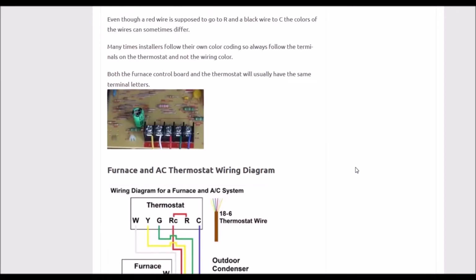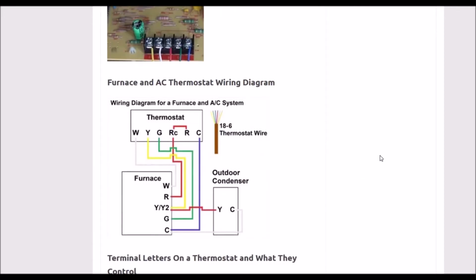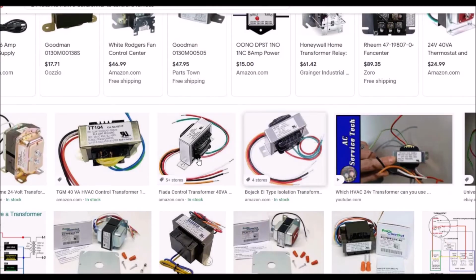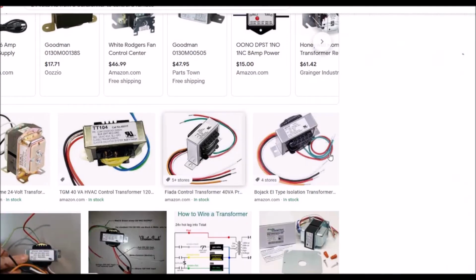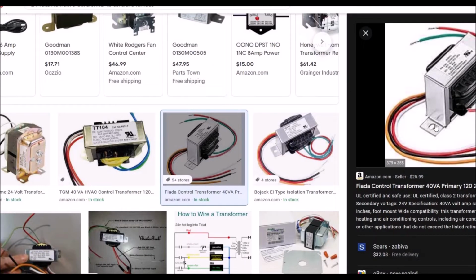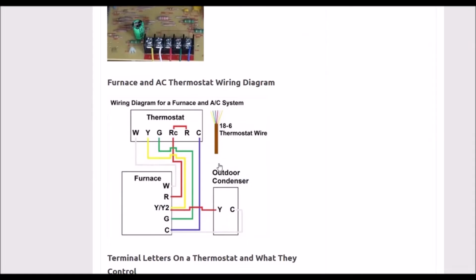And so what wires would all this be coming in on, and how would this be wired up? Here's an example of a basic thermostat and furnace wiring. The transformer, 24 volts, will be coming in on R right here. It's hot. And the common leg of the transformer is coming in on C, which is the common leg. Take another look over here. On one side you would have 120 volts coming in, and on the other side you'll have a common and a hot on these two wires that are coming out on the 24 volt side. These two wires are basically the common and the R.